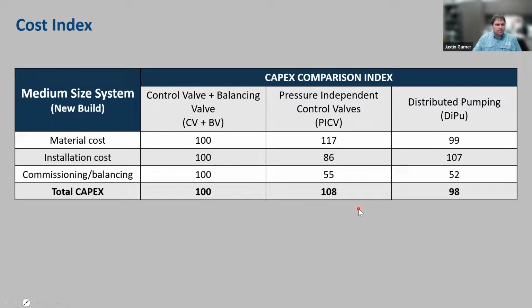I appreciate the fact, Pete, that you guys did not completely eliminate commissioning and balancing, because I've been told by others that with pressure independent control valves, or even an alternate technology, you don't need to do water balance anymore. And as I stated in one of the previous slides, you still have to ensure flow. Just with a pressure independent control valve, you still have to ensure the valve is set up correctly. You still have to set the right DP set point in the system to get the valves in control. So you're not eliminating the testing and balancing cost, or definitely not the commissioning cost.